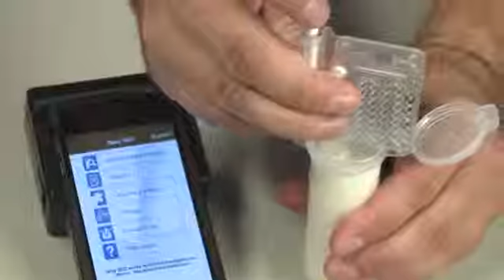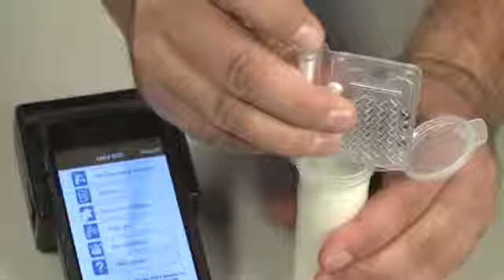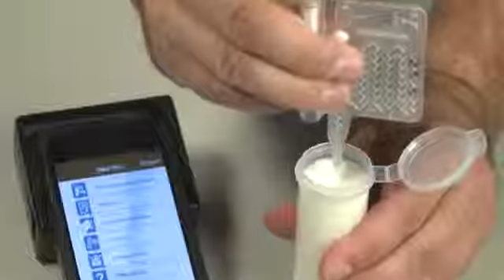Taking a milk sample. Using a milk vial, insert the slide into the milk. To ensure you get the necessary amount of milk for an accurate test, please do the following. Make sure the slide tip is fully inserted into the center of the milk. You may have to tilt the vial to ensure the slide tip is fully immersed in the milk. Press the piston only when the slide is fully immersed in the milk. You will know you have the correct amount of milk when you see the milk pass through the middle of the third column of tracts or capillaries.